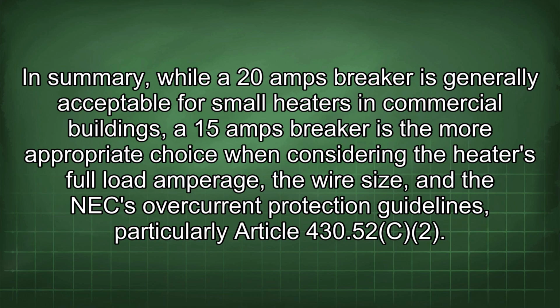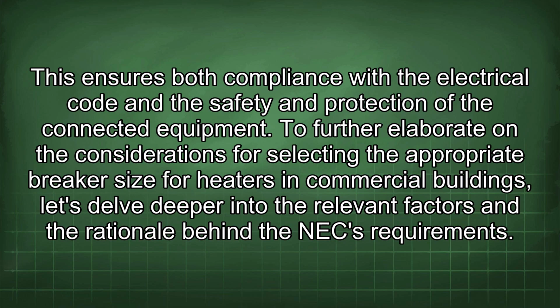In summary, while a 20 amps breaker is generally acceptable for small heaters in commercial buildings, a 15 amps breaker is the more appropriate choice when considering the heater's full load amperage, the wire size, and the NEC overcurrent protection guidelines, particularly Article 430.52 C2. This ensures both compliance with the electrical code and the safety and protection of the connected equipment.